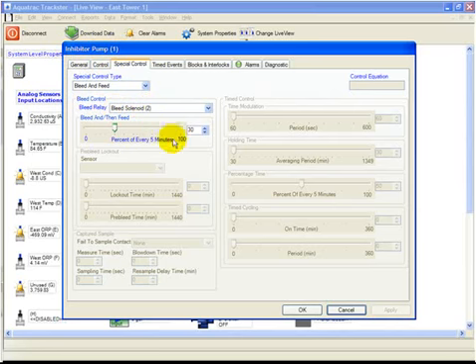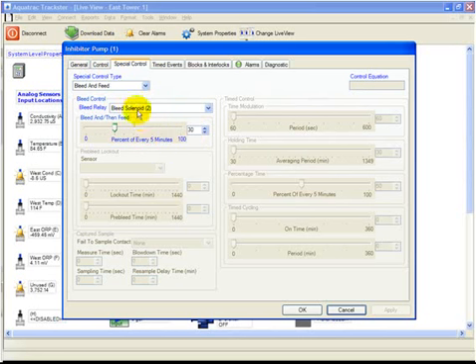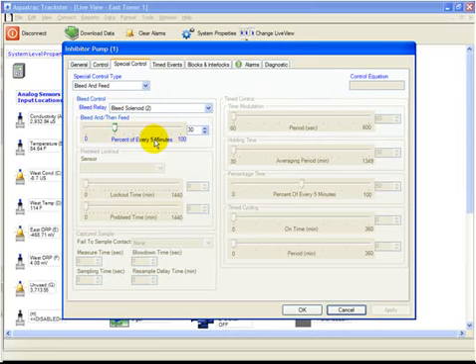And we've entered in 30% of every five minutes. So what will happen here is when the bleed solenoid turns on, the inhibitor pump will turn on simultaneously. The inhibitor pump will turn off after 30% of the first five minutes.